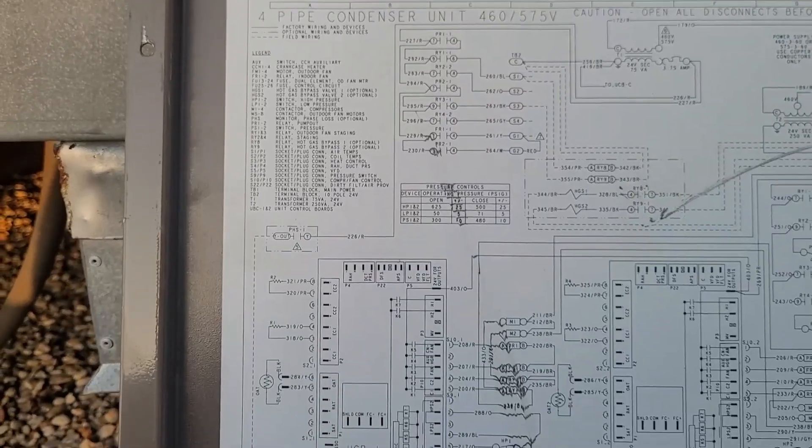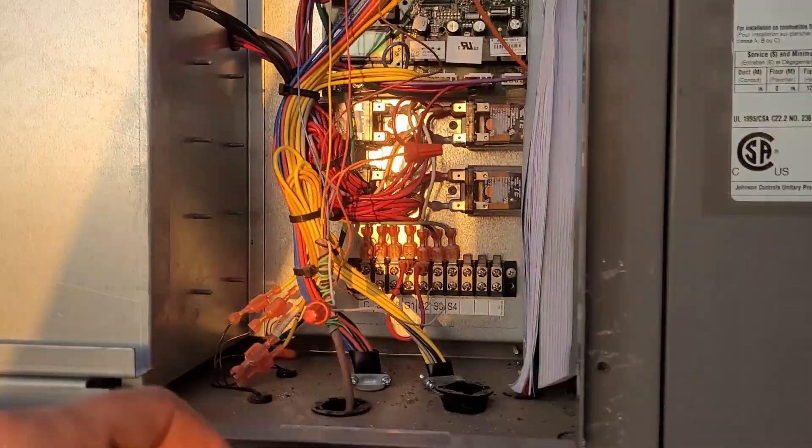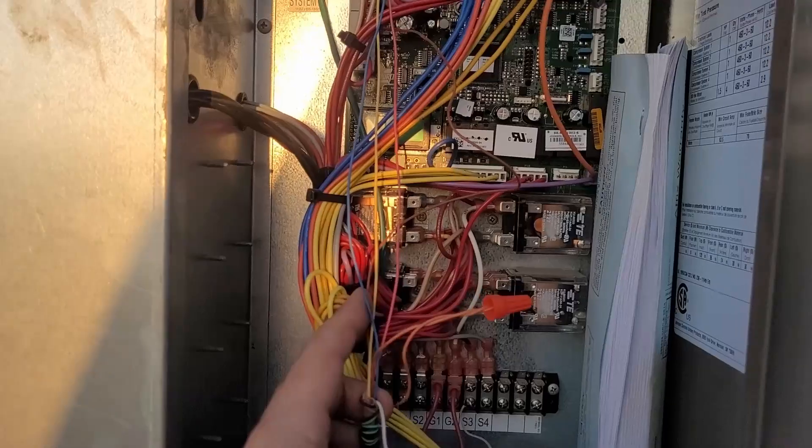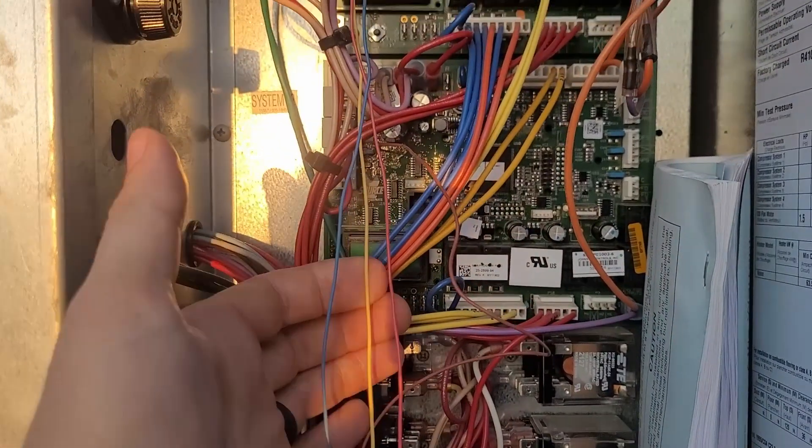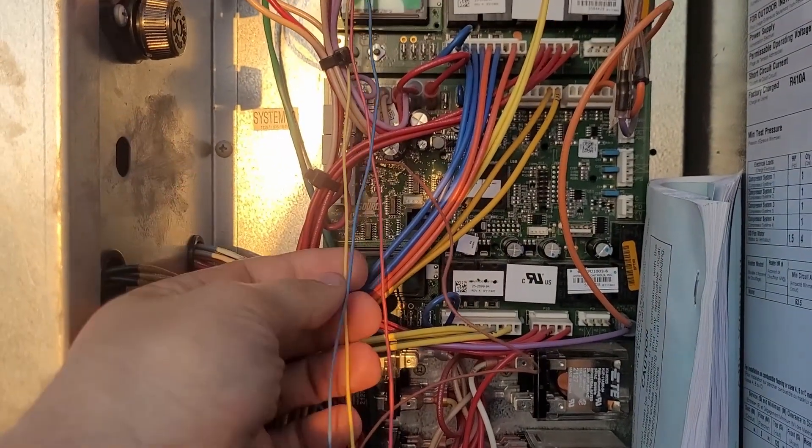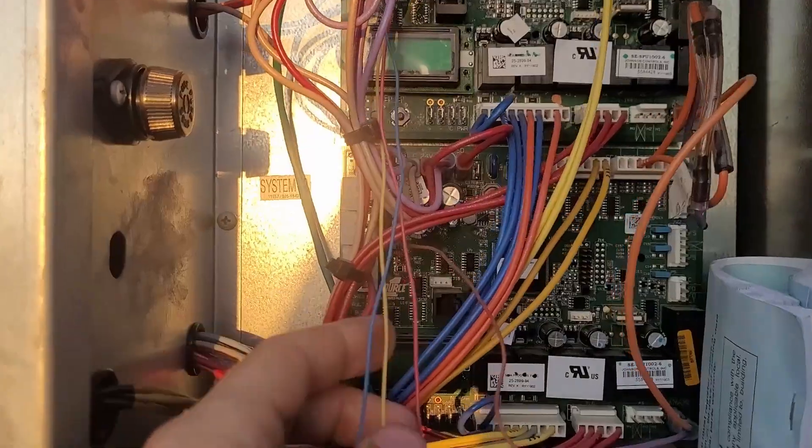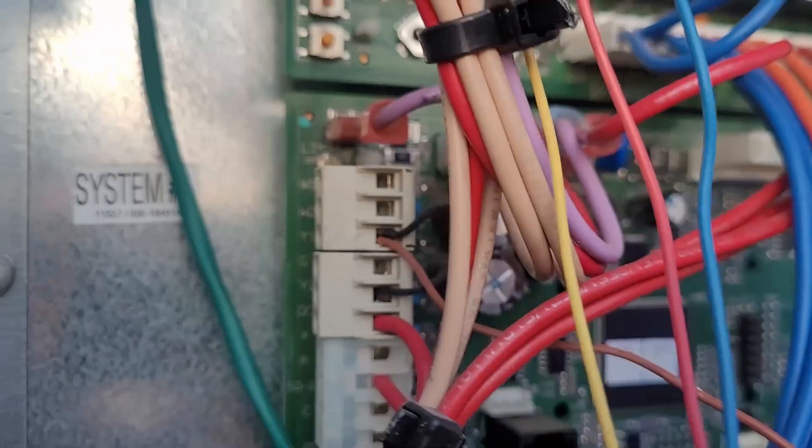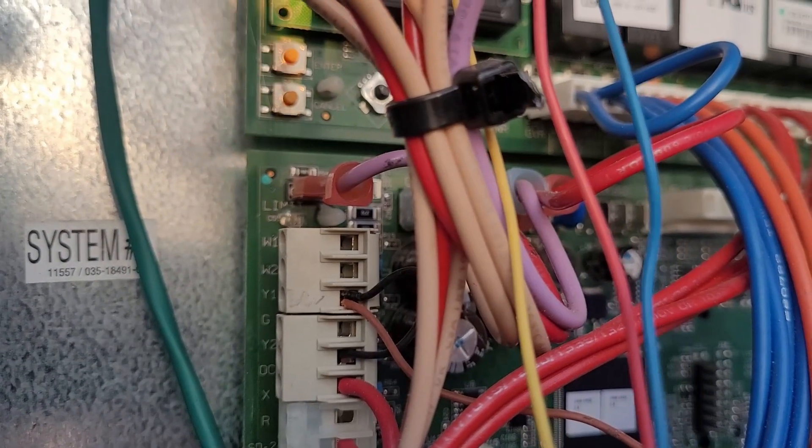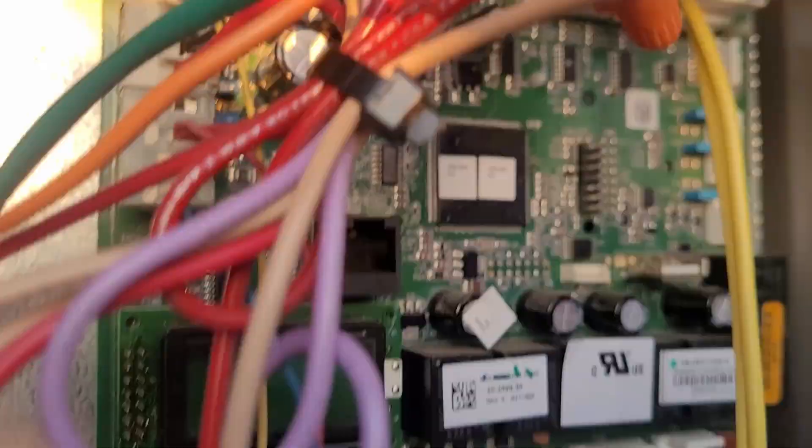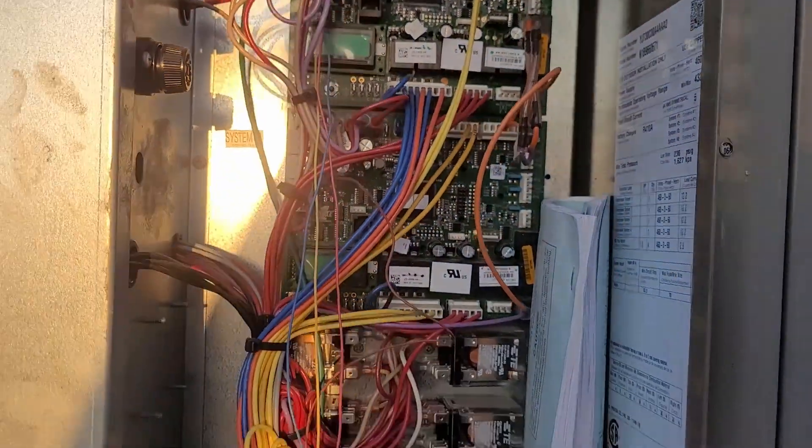The way it's supposed to happen, you have your calls come up on two wires. In our case, it's yellow for first stage and brown for second stage, and they go into these terminals. So those are your calls.